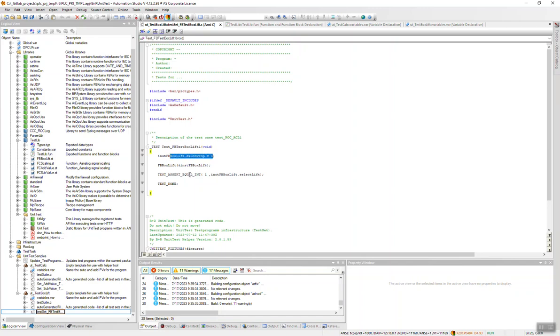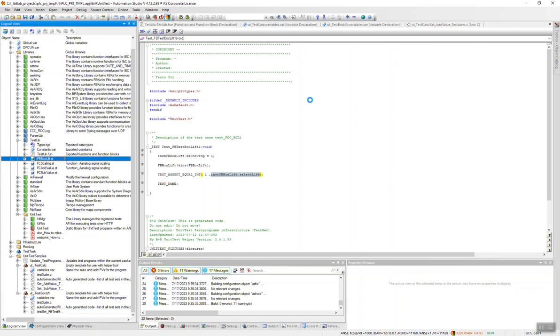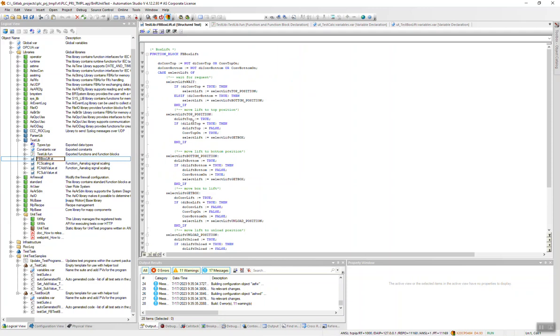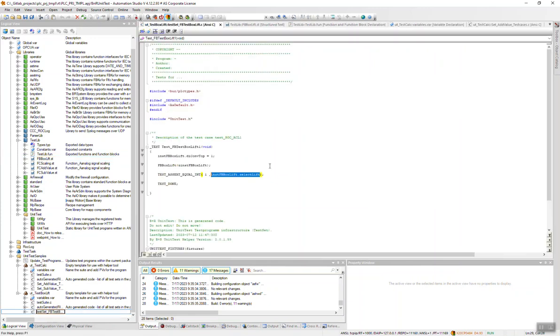This variable is actually a state of this FB. What does it mean? Let's open the FB box lift. You see this is the state called select lift, it's an enum. What I did is I forced this value to true. If this is true then it goes to the next state which is this one, so it is one. That's exactly what we try to do here. Force it to one, call the instance of the function block, and then the state should be one which is done, then the test is done. As simple as that.